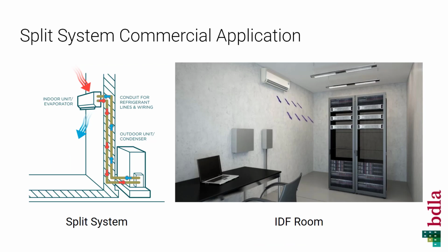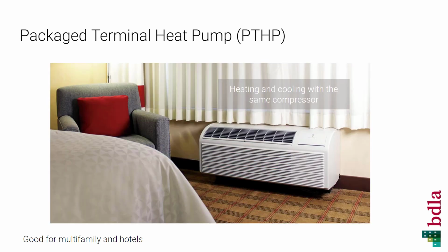Split systems can actually be used in commercial applications as well, typically when there's one single room that has a large cooling load, like an IDF room where there are large server banks that need a lot of cooling, but the surrounding areas don't need the same amount of cooling. So that is a common application of a split system. Packaged terminal heat pumps, or PTHPs, are very common in hotels. This picture is actually a hotel setting where each room needs individual controls, so they are installed directly through an exterior wall. In the same unit, they're able to reject heat or pull heat from outdoors and expel it into the room without any need for ductwork or piping or anything.